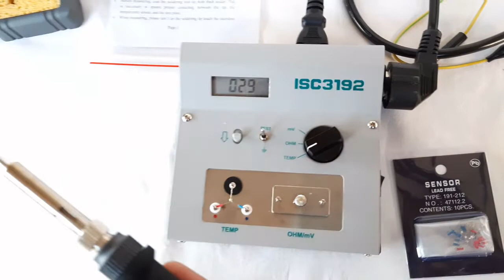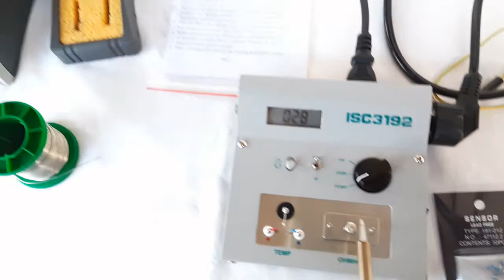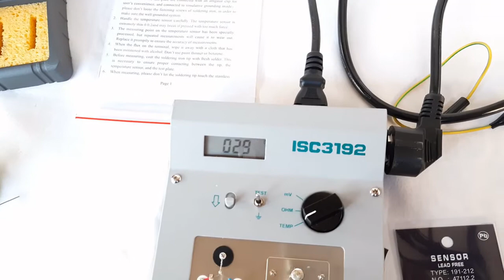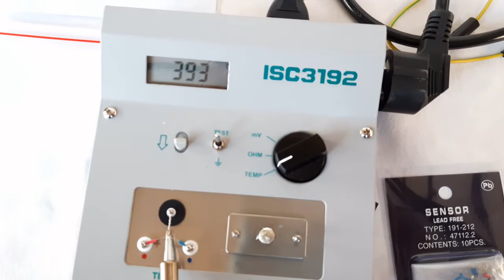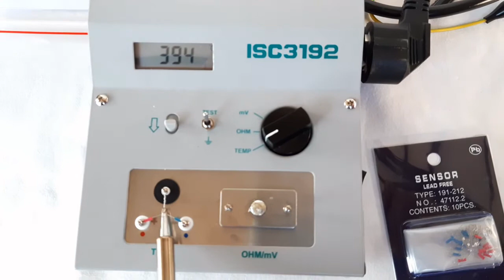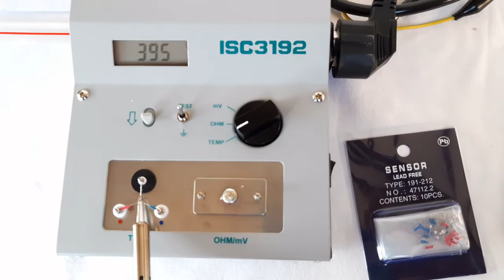We will check the temperature of this soldering station. First we need to apply some fresh solder on this soldering tip, and this soldering temperature should be more than 350 degree, then we need to touch this soldering tip at this terminal. See, this is now displaying the actual temperature. However, set temperature is 350 degree and the actual temperature which we have measured on this thermometer is 395. So we need to calibrate this unit, which we have explained to you earlier.